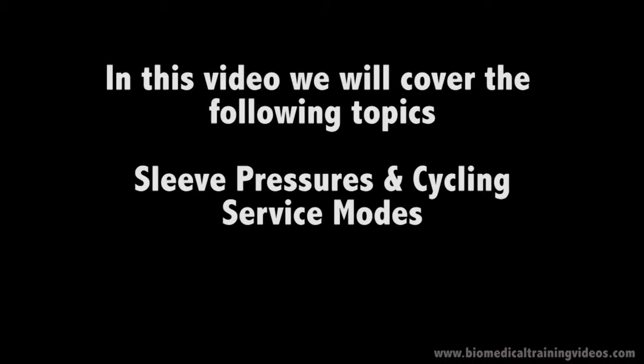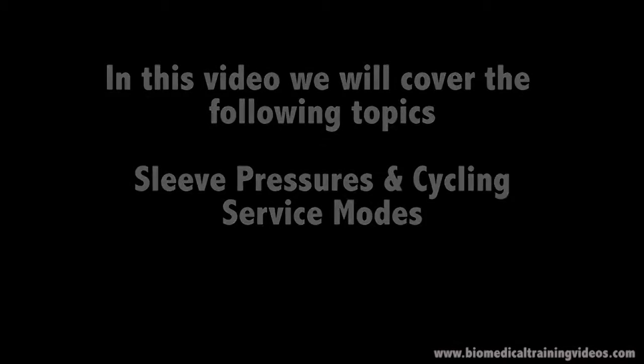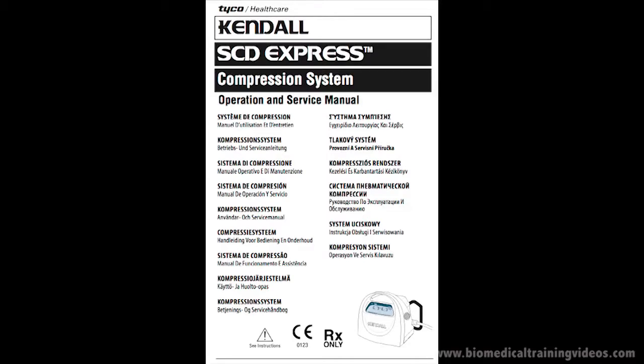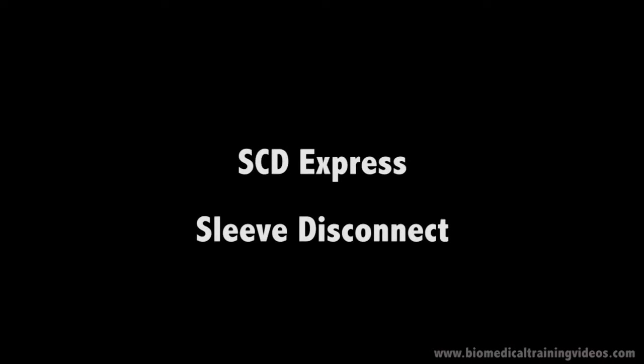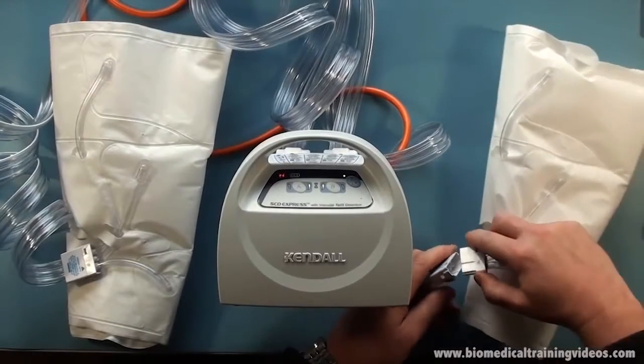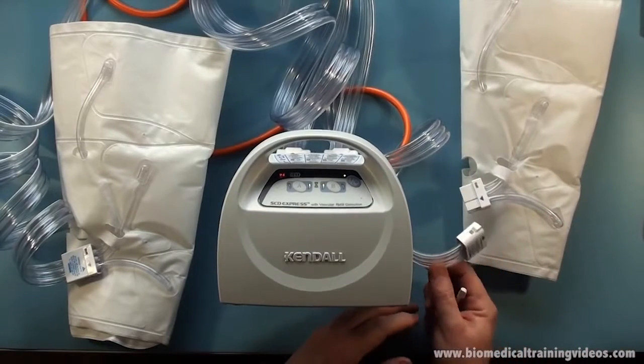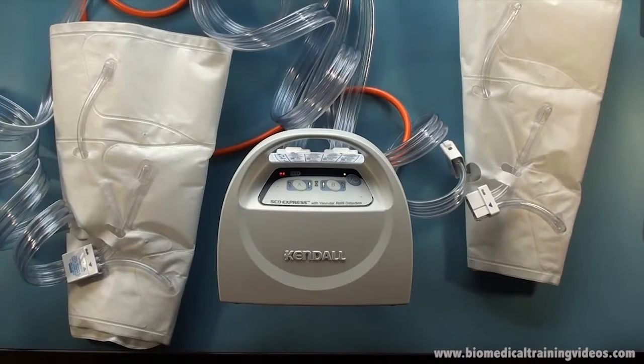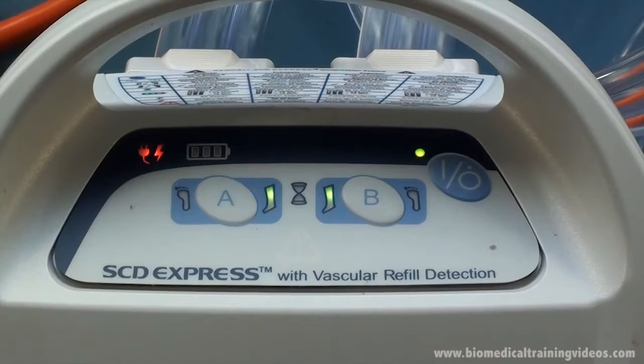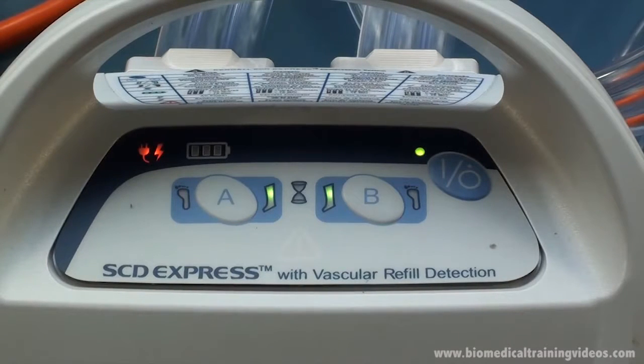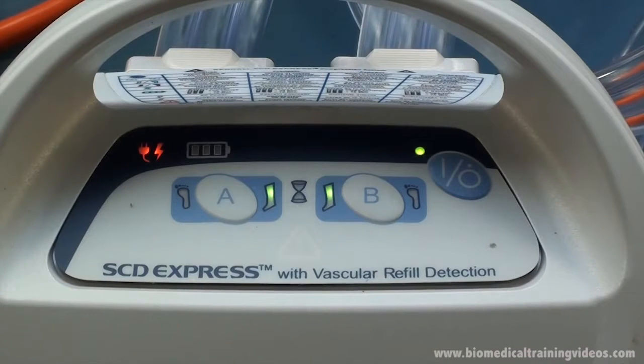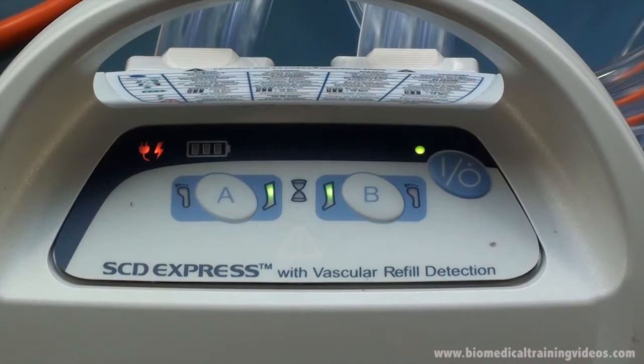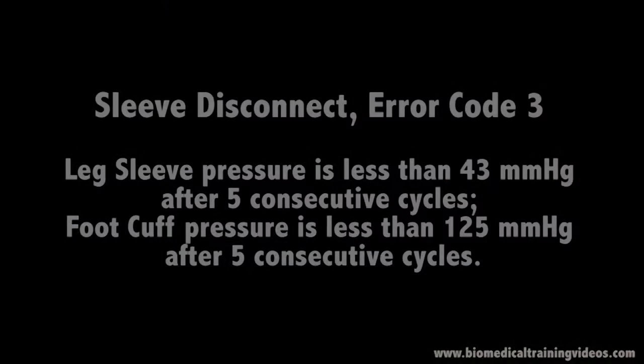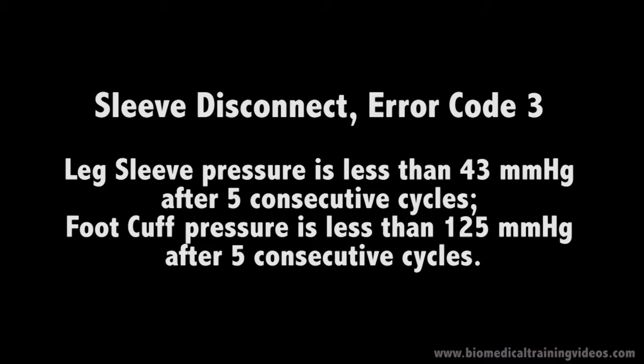In this video we're going to be talking about sleeve pressures and cycling, and also cover the service modes. We're going to make reference to the service manual. So in the first part, just going to try and demonstrate the sleeve disconnect. If you unplug one of the sleeves, you don't immediately get an error to indicate there's a leak. In fact, it takes 5 consecutive cycles before an error code 3 is generated.